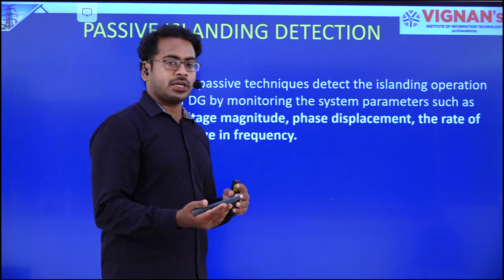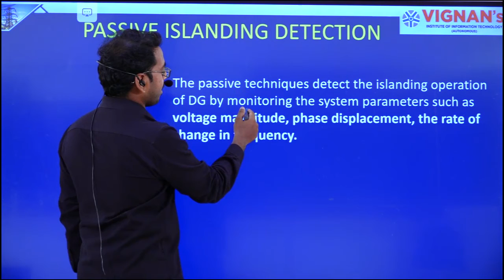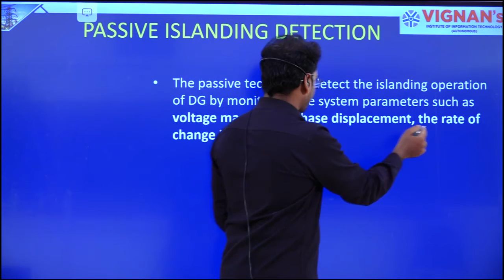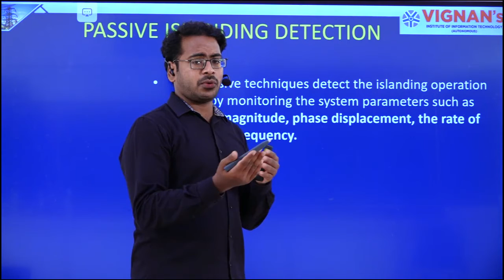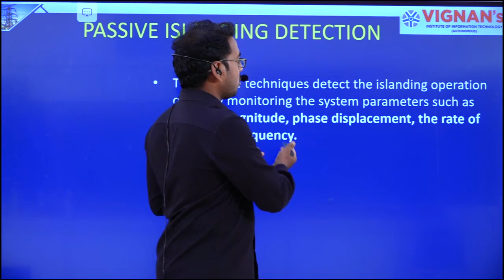Now passive islanding detection. Passive islanding detection means, as I already told you, we have to measure some parameters at the point of PCC. The passive techniques detect the islanding operation of the DG by monitoring system parameters: voltage and phase displacement, rate of change of frequency. We measure the rate of change of frequency at PCC, the voltage magnitude, and the phase displacement. Based on it, we detect the islanding. That is called passive islanding.